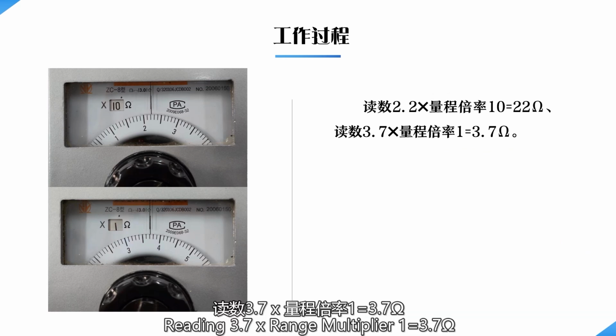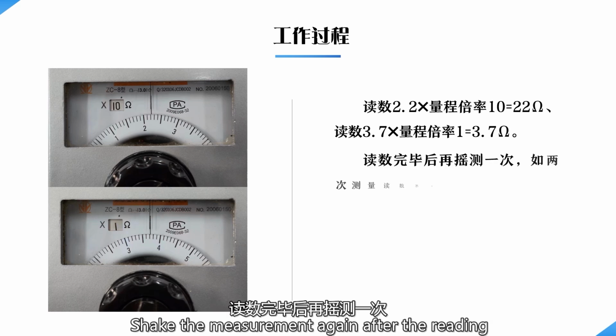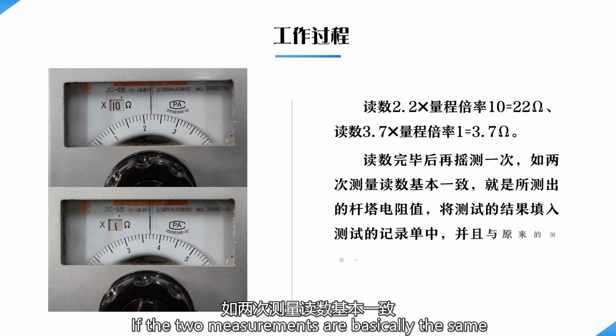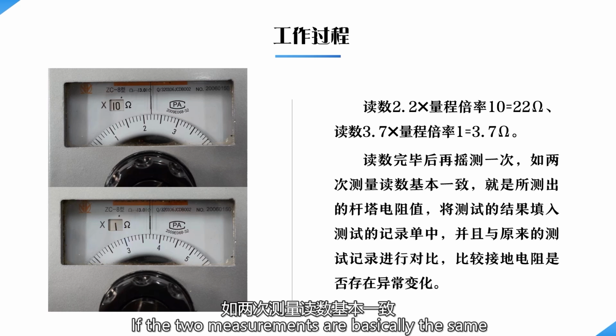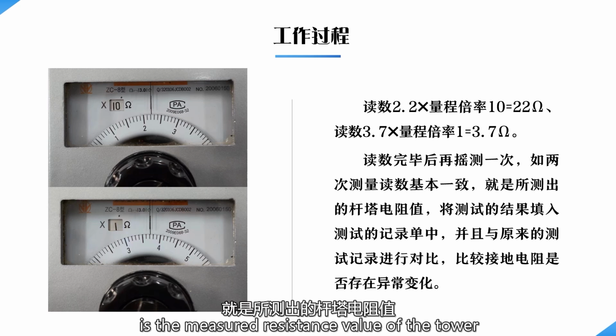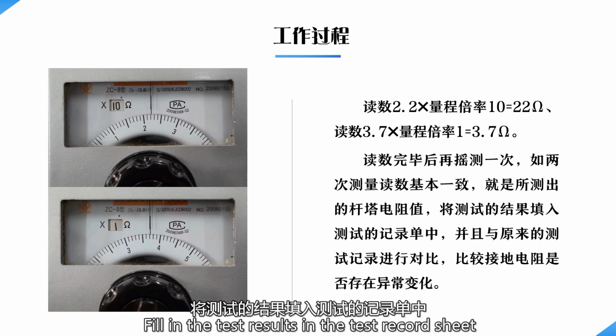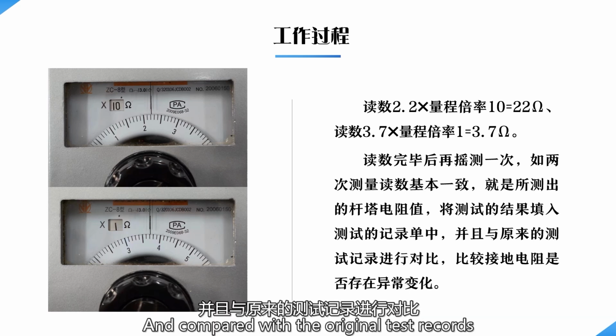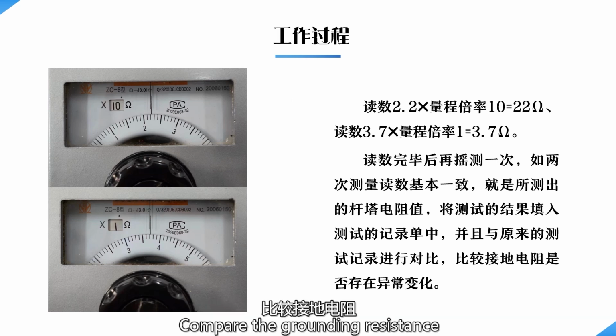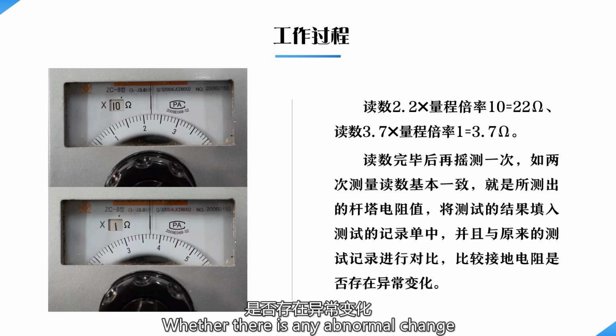Reading 3.7 with range multiplier 1 is 3.7 ohms. Shake the meter again after the reading. If the two measurements are basically the same, that is the measured resistance value of the tower. Fill in the test results in the test record sheet and compare them with the original test records. Check whether there is any abnormal change in the grounding resistance.